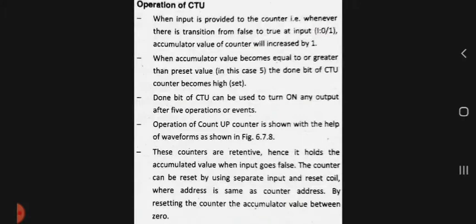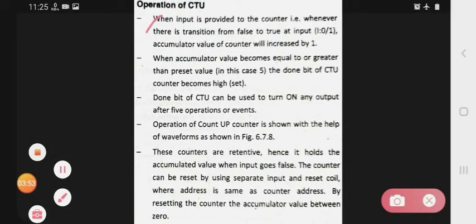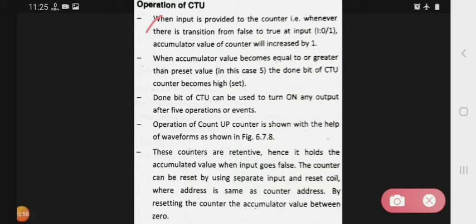Now see the operation of CTU. When input is provided to the counter, whenever there is a transition from false to true at the input, the accumulator value of the counter will increase by 1. Means, jabhi bhi hum counter ko input provide karenge, aur false se true condition hogi, tab accumulator value increase by 1 hogi.